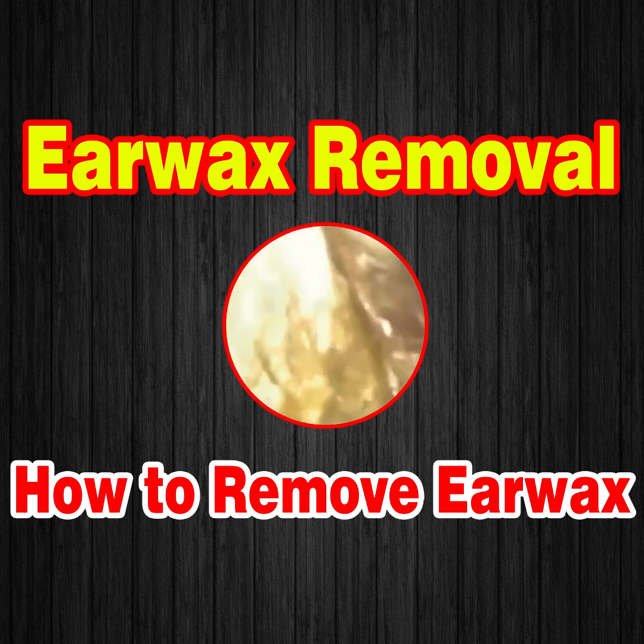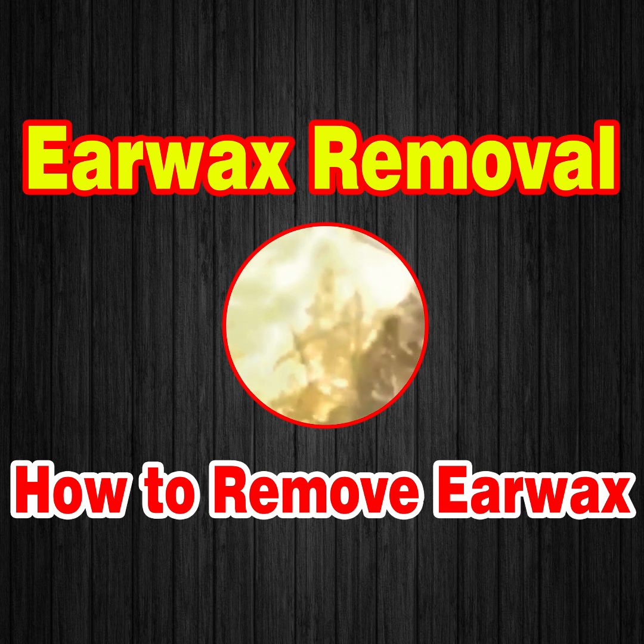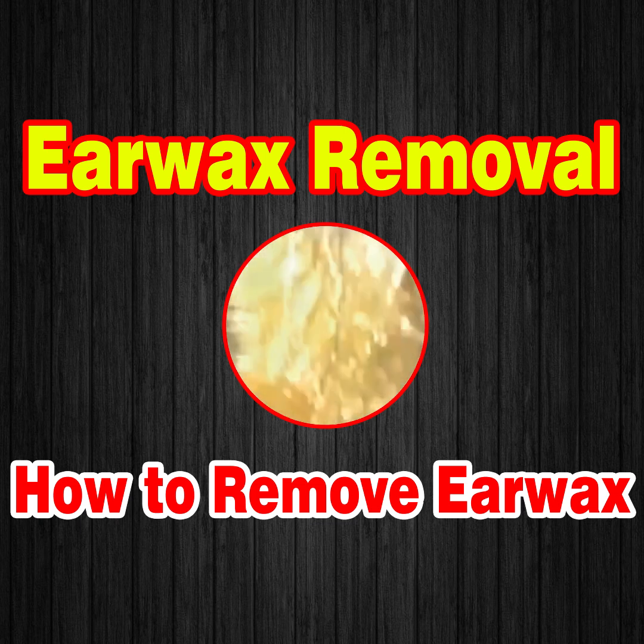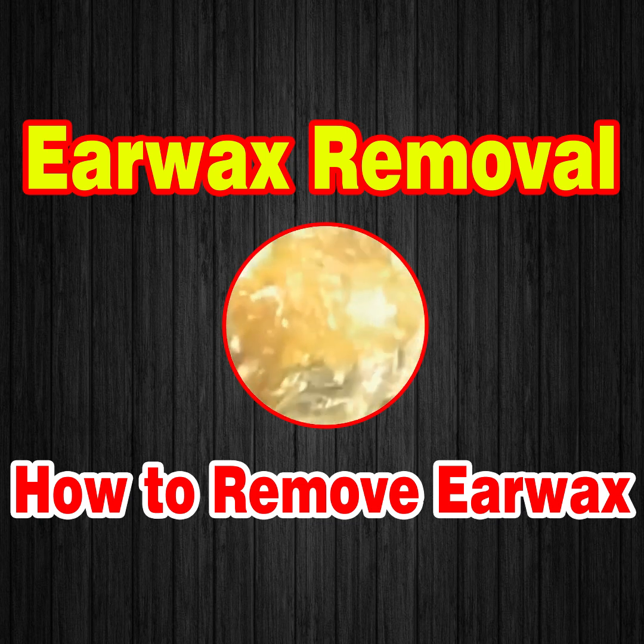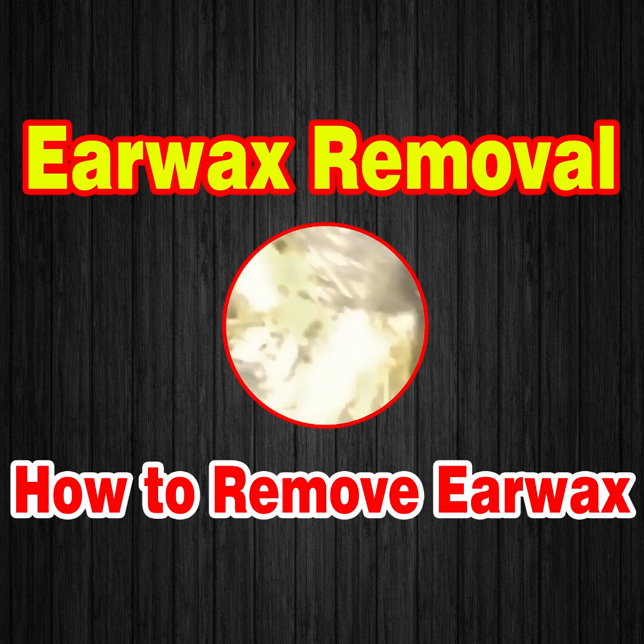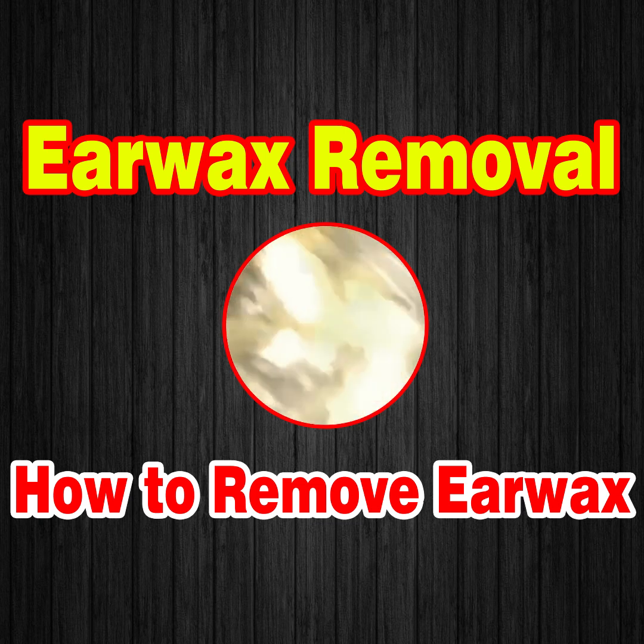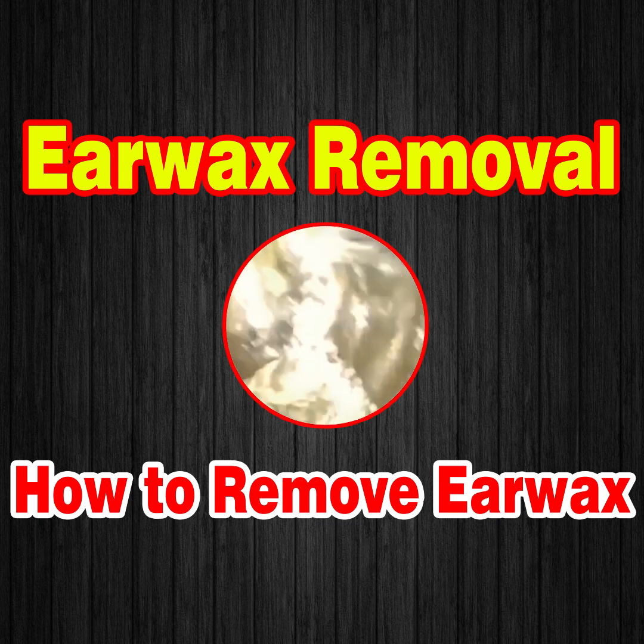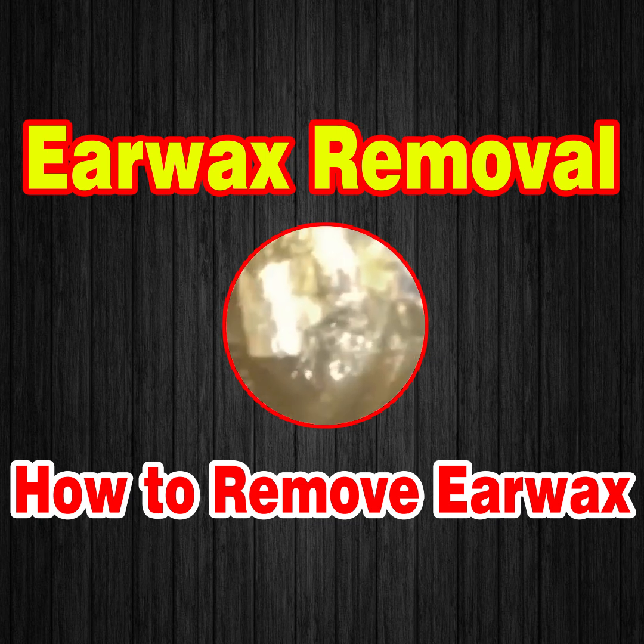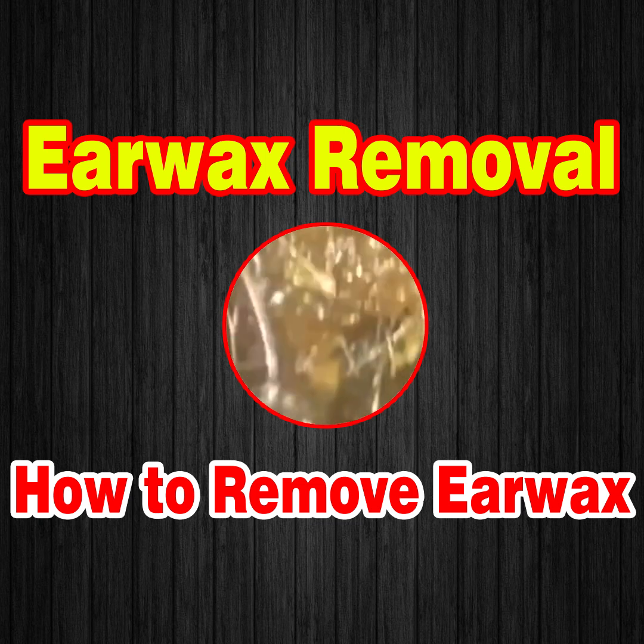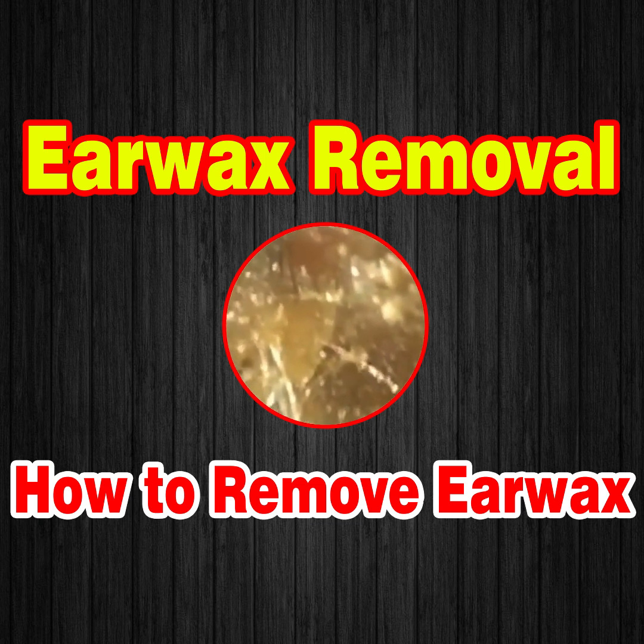I'm using our standard speculum size, which is a size 2, which has an internal diameter of 4.25mm. So it's in keeping with the normal specula that most audiologists use to examine the ear, at least for adult patients. We have got a smaller size speculum as well, for narrower pediatric ears, and that's got an internal diameter of 3.5mm.